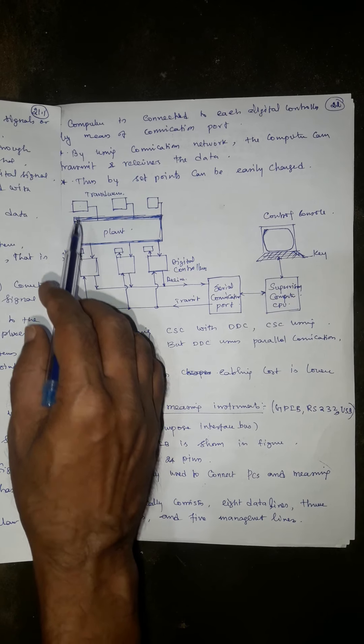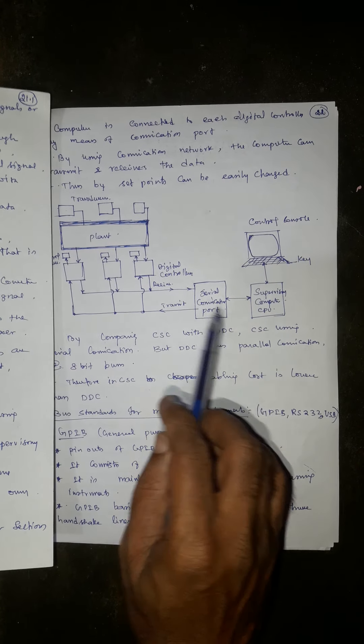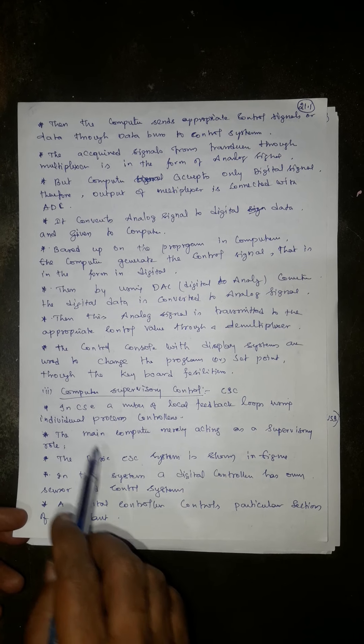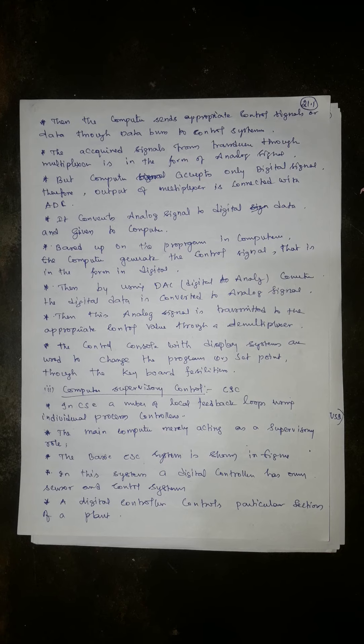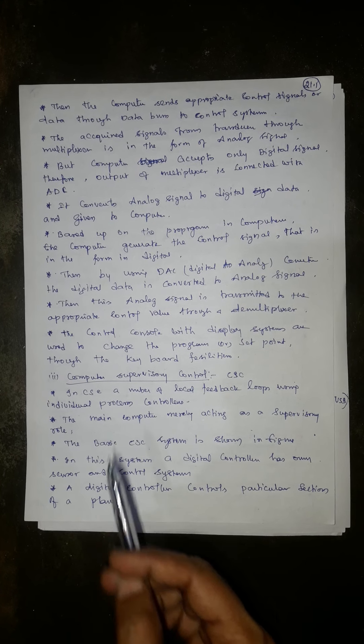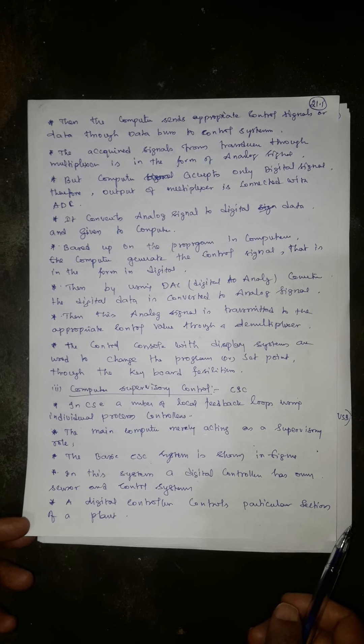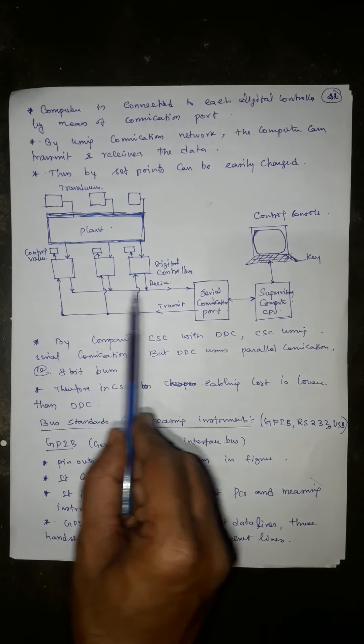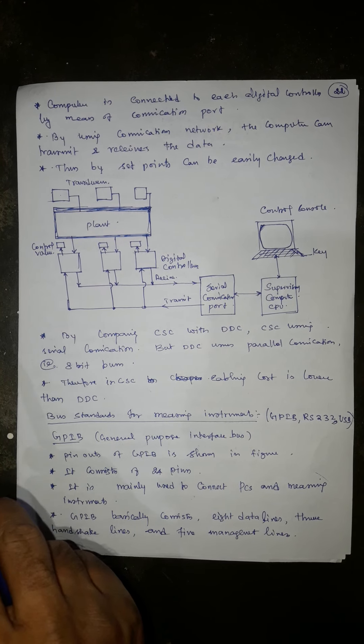In CSC, each digital controller has its own transducer and control system, including a control valve or solenoid valve. Each control box manages a particular section of the plant and is connected to the supervisor computer through a serial communication port. By using a communication network, the computer can transmit and receive data. The main computer merely acts in a supervisory role, while set points can be changed using the console and programming keyboard.